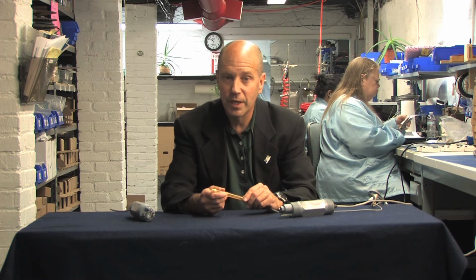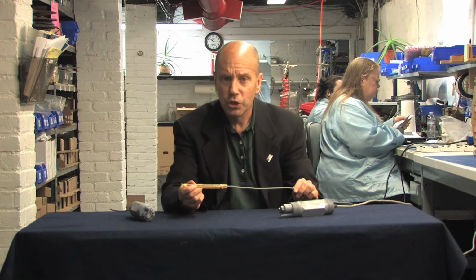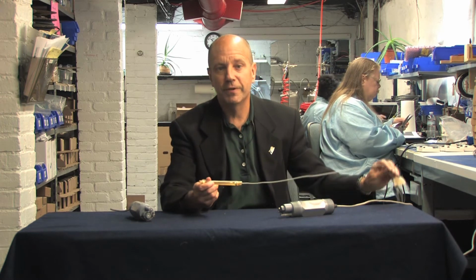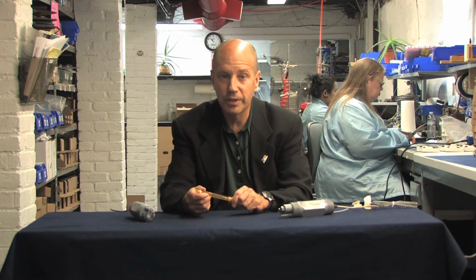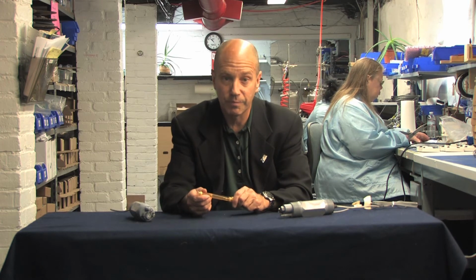A second limitation is the size of the signal that the probe generates. All pH and ORP probes are like batteries. They produce a voltage. However, the current they produce is tiny, on the order of microamps. The tiny current means that the cable length is kept short, usually no longer than 10 feet, to prevent the degradation of the signal. And lastly, most probes lack a temperature element, so that compensating the pH measurement for temperature is not possible.